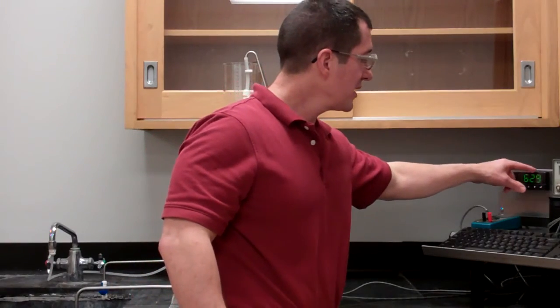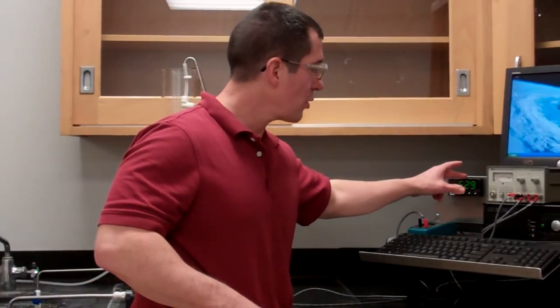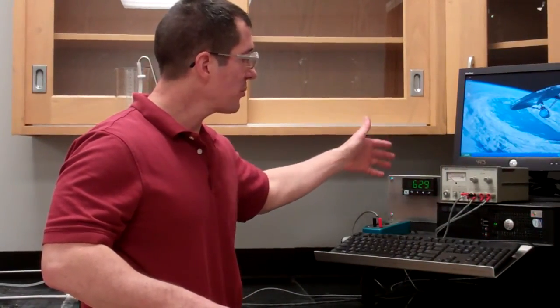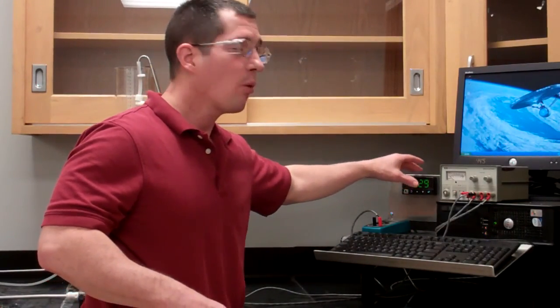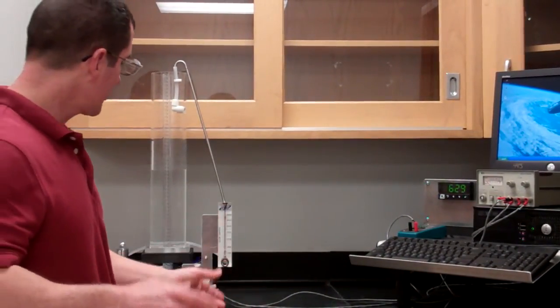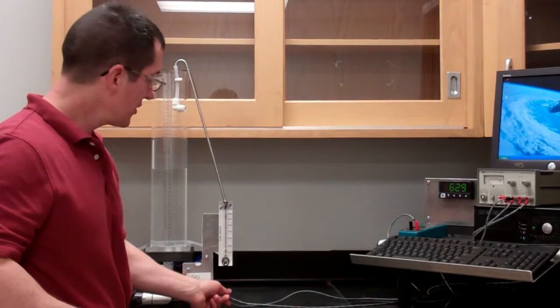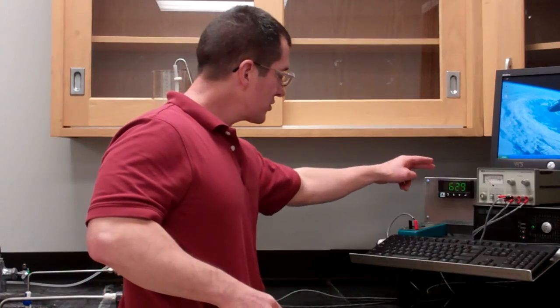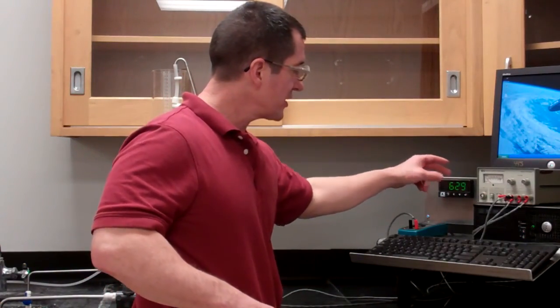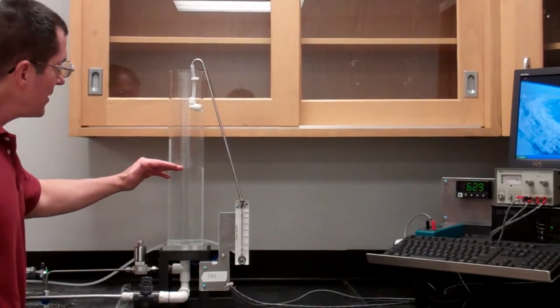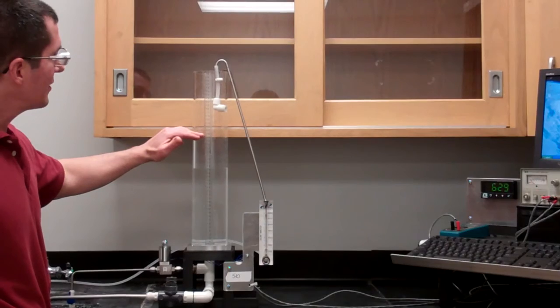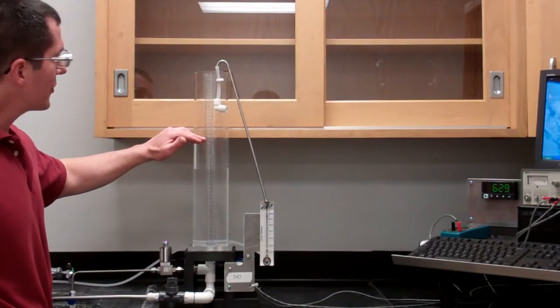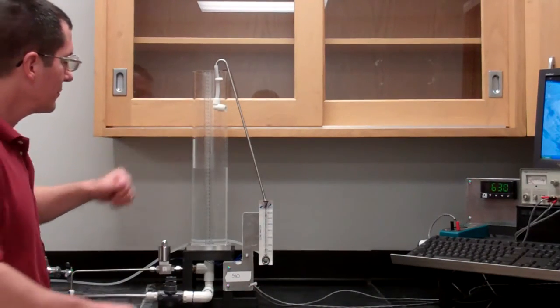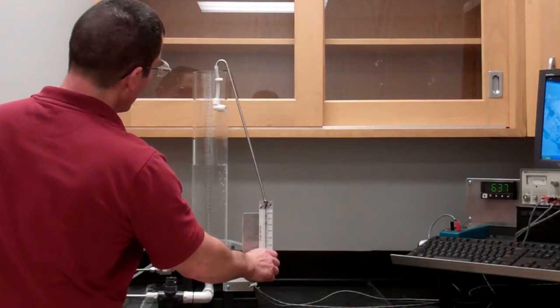The display is just in counts, which isn't any kind of engineering unit that you're going to use. However, the controller makes control decisions based on that. I think it's important for us to start understanding what the controller sees and what it makes decisions on. What it sees is the output of this transducer. This transducer has an output that goes to the controller, and that's the signal the controller sees. Now there's going to be some set point, and the set point may be some height in the tank. Let's say we want to control the water level in this tank to 30 centimeters of water. So take this up to about 30 and see what the output on our transducer is.